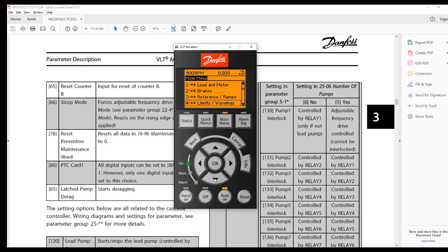The deragging has a speed setting in it, but the ramp times are based on the ramp times you set for your application. Think of deragging as an add-on feature. It's not motor control per se, because everything should be preset in the drive for motor control. You want to set up the drive, do the AMA, do your ramp times and stuff for the application where it can run the application. Then DERAG is an add-on feature, another layer for clearing the pumps. But the motor control stuff, we're still using the motor control to start and stop it. And all the ramp times that you would use are in play.